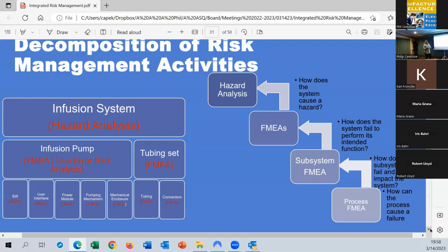So I like to decompose my risk management activities, just like system architecture, right, where you decompose your system into different parts. I like to do the same type of decomposition with my risk management activities. So I have hazard analysis at the system level. I'll do FMEA of the different parts of the system, and then even components within that system, I can do FMEA. And then I can relate them all. So I can do a process FMEA of a part that I built, right? And I can link those end effects to the higher level. I can do subsystem FMEA and link those end effects to the causes in my FMEA. And the same, the end effects of my FMEAs, I can link to my sequence of events in the hazard so that everything is related.